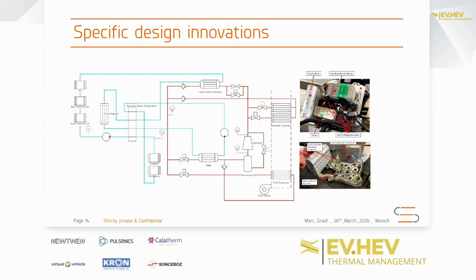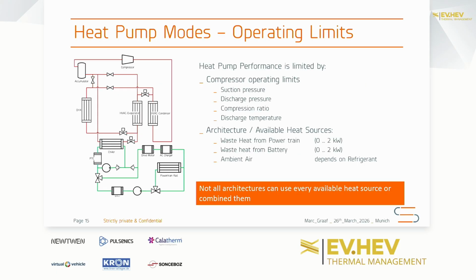Of course, everybody knows the octovalve and other module buildings in Tesla. There's a lot of information on that available, but we summarize this also for some less known vehicles. And then, let's say we get to the more detailed conditions that are interesting for our operation.